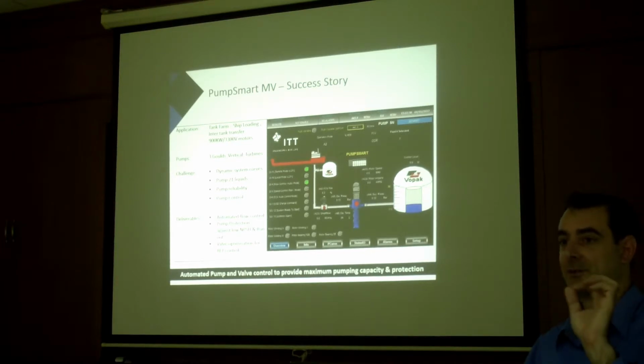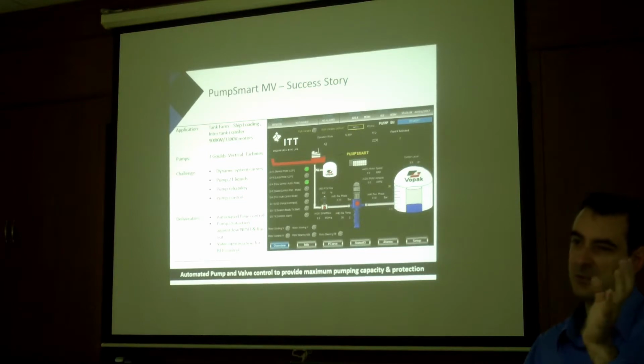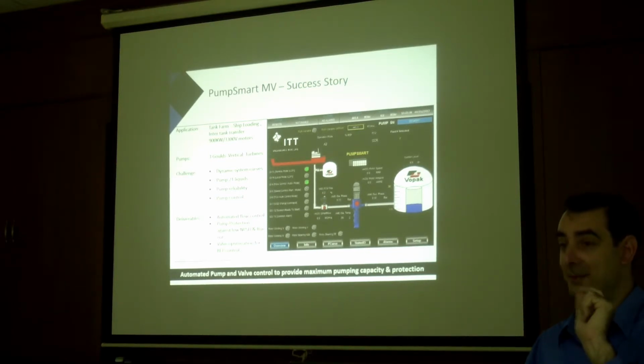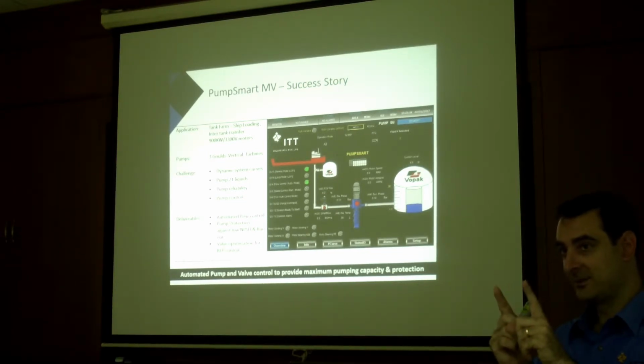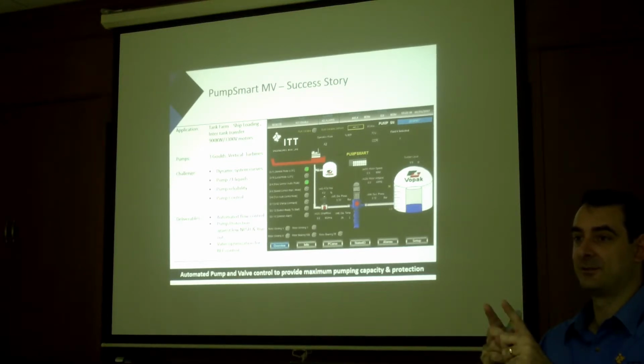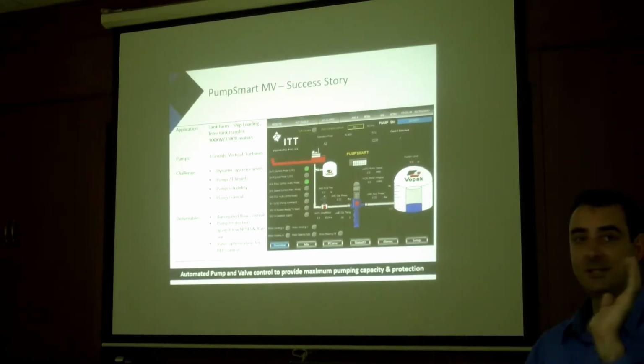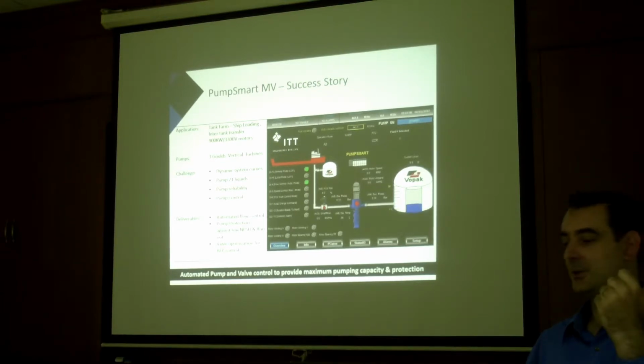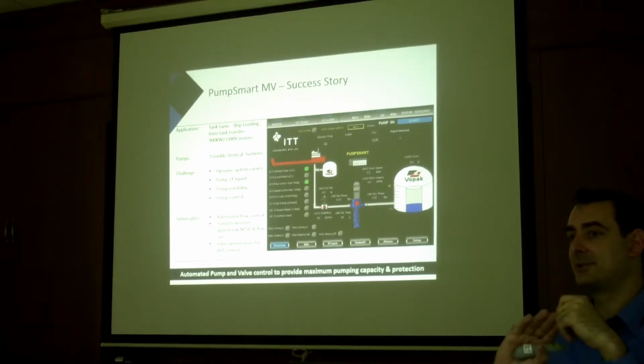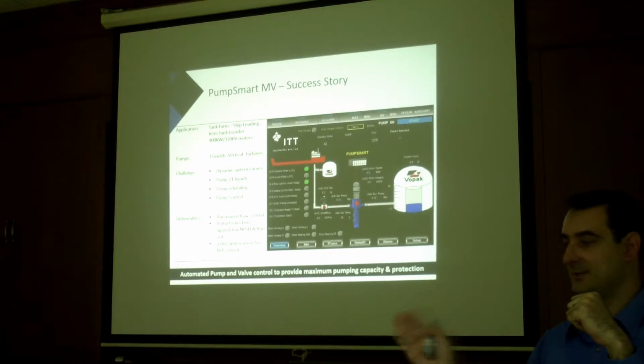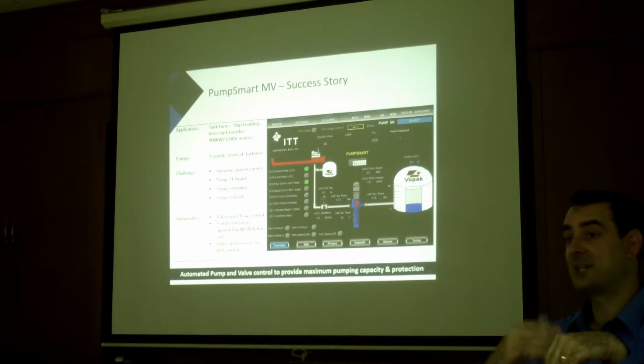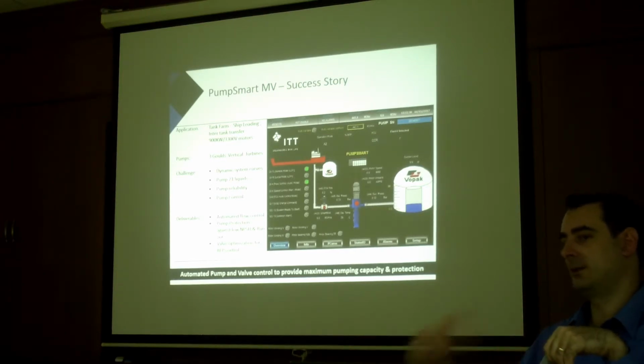Yep, yep. So in the past, they had to calculate the flow, where it is on the curve and all this. But now, on the PumpSmart screen, it'll tell you the percentage of best efficiency point, BEP. Because it tells you the BEP, that's the only value you need. You don't need to know the speed, you don't need to know the flow. You just need to know how far past the best efficiency point it is and push it back. And then they can set it and leave it. But if they change the liquid, they need to do that again.